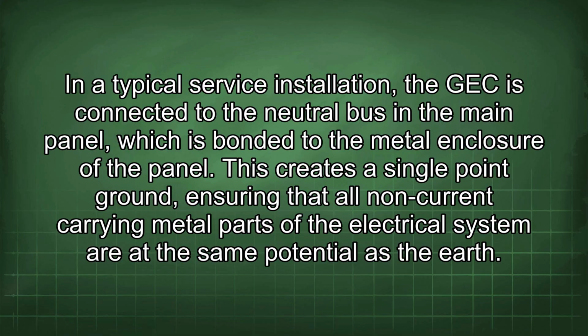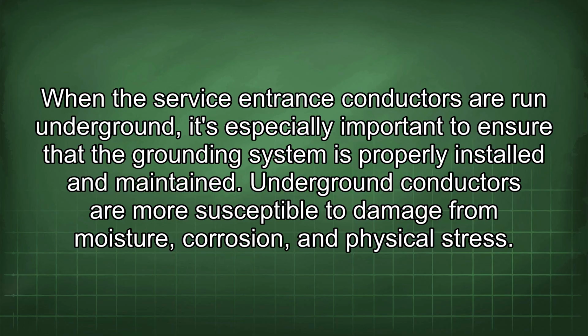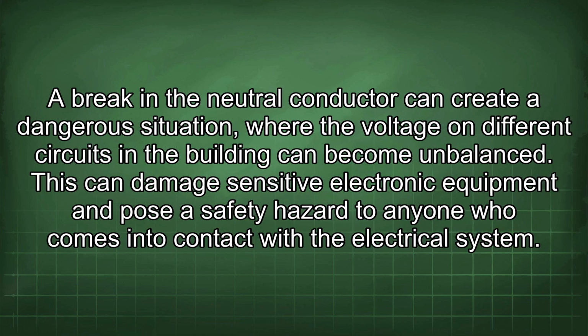When the service entrance conductors are run underground, it's especially important to ensure that the grounding system is properly installed and maintained. Underground conductors are more susceptible to damage from moisture, corrosion, and physical stress. A break in the neutral conductor can create a dangerous situation where the voltage on different circuits in the building can become unbalanced. This can damage sensitive electronic equipment and pose a safety hazard to anyone who comes into contact with the electrical system.